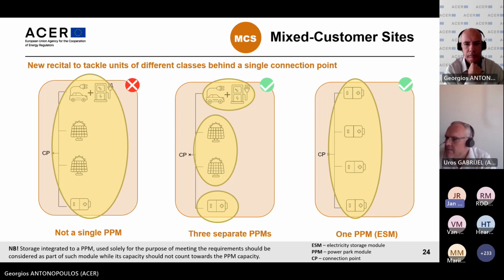My point is, if you have 50 megawatt of wind, 50 megawatt of PV, and 50 megawatt of storage, the whole installation should respond as 150 megawatt PPM. If you have, for instance, a low LFSM-U situation, and we would make a 60 or 75 megawatt grid connection, we cannot do that because we have to respond as a 150 megawatt plant, and this is really bad. We should really consider how to deal with this.